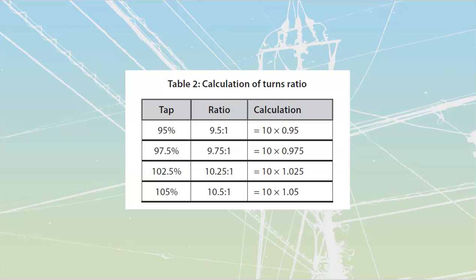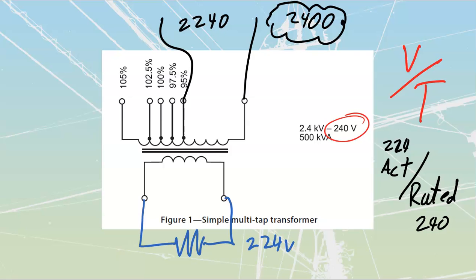At 100%, and that was not shown, it should be right here in the very middle of the table over here, we would have a 10-to-1 ratio. Right now, we are at 95%, which means that we're going to take 10, because that's what our 100% ratio is, times 0.95, which gives me a ratio of 9.5 to 1. In other words, my voltage ratio on the low side is going to be 9.5 times smaller than what's on my high side. What do we have on our high side?